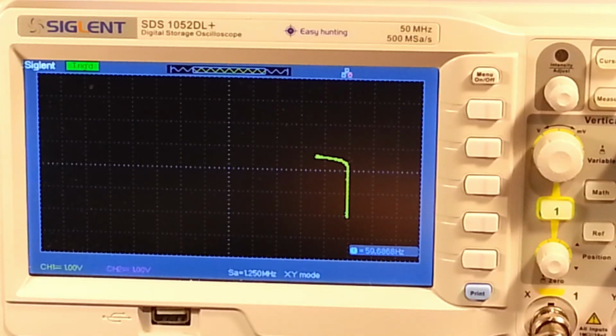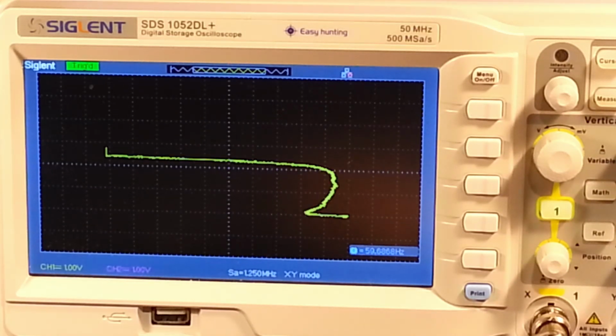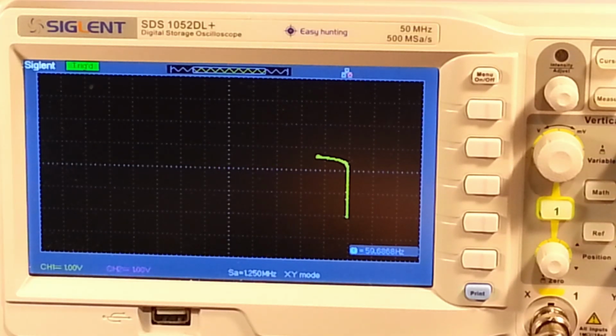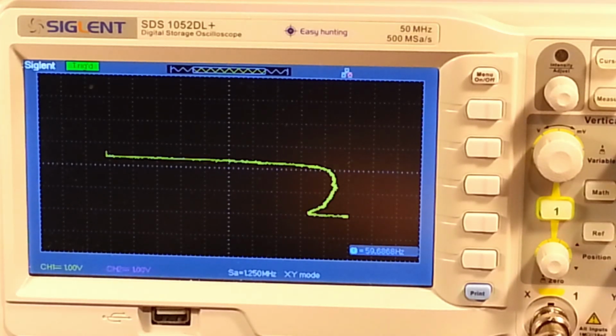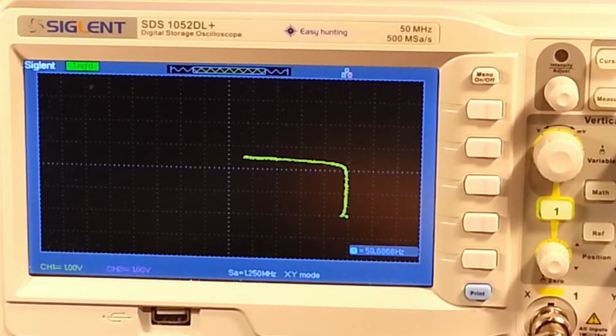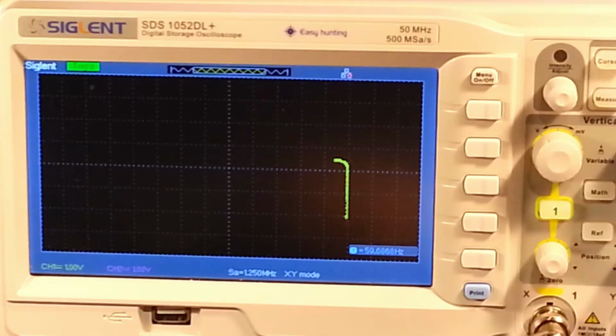So basically for each setting I have, that's the 100, that's the 10. If I go down to 10 microamps and then change the switch to 1, notice it picks up the fact that there's 1 microamp of current sneaking through that junction. But if we push it to 10, it's providing a little more resistance because it's not fully broken down for that much current at that voltage. But if we put it up to 100 microamps, you have to apply a little more voltage to it in order to get that junction to break down and flow more current through it.